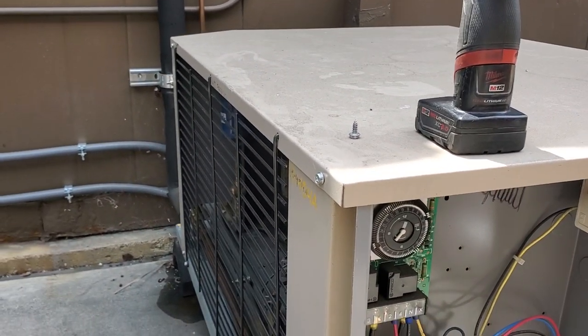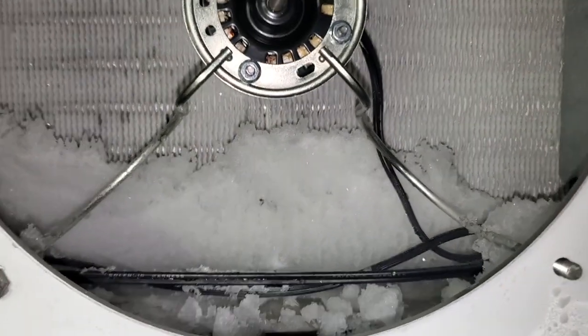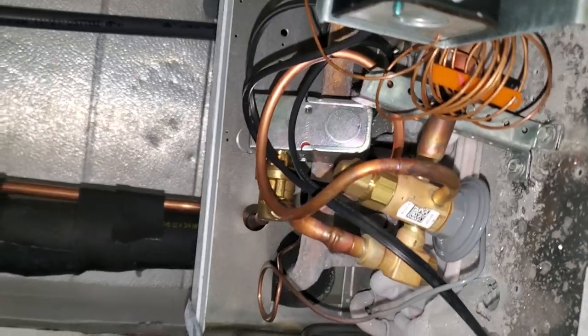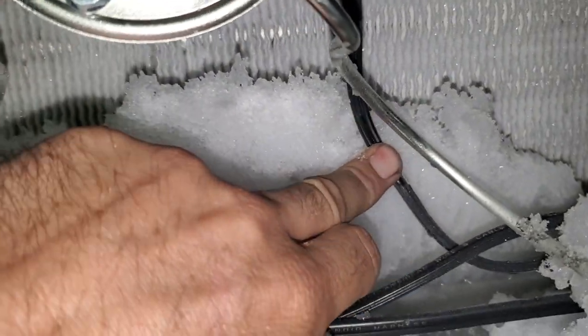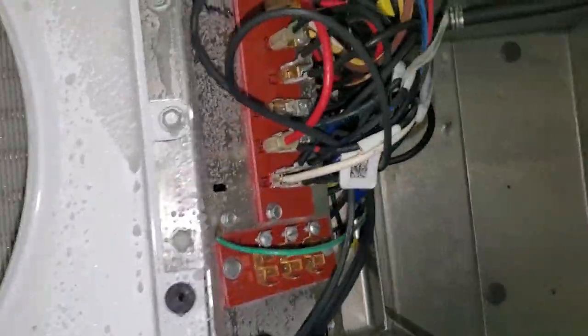We're going to go ahead and go inside and look at that vibration in the evaporator fan blade. There's quite a bit of ice, and there's no way that's just from this morning. I'm going to go ask them what breaker they were resetting. This is interesting — for a unit, it doesn't make sense that there's that much ice. I'm not seeing anything scary jumping out at me. I don't see anywhere where the wire's rubbed out yet.